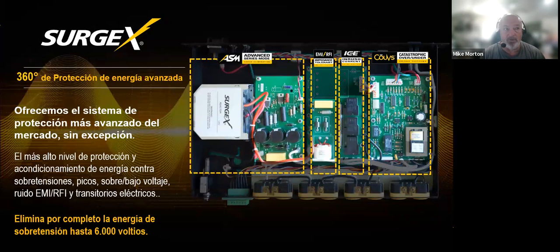We then go into another area called inrush current protection, or ICE. This area will not eliminate, but minimize the amount of inrush of current when you turn devices on. Here's the example. If you have a PDU and you have several amplifiers plugged into that PDU, an amplifier may only run at, let's say, 5 amp when it's running. But when you turn it on, it can actually absorb as much as 20 amp of power when it first turns on, because it has to energize the capacitors inside the amplifier. If you have multiple devices plugged into that PDU, that can cause a significant power draw and damage to devices that are plugged into that PDU. So what we do is we actually stage and stagger the inrush of that current so that it's well within the realm of the PDU's capabilities and actually makes it safe for all the devices that are plugged into that unit.